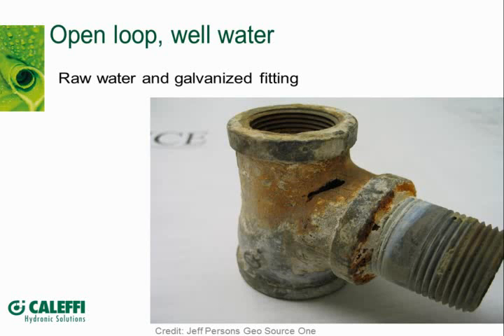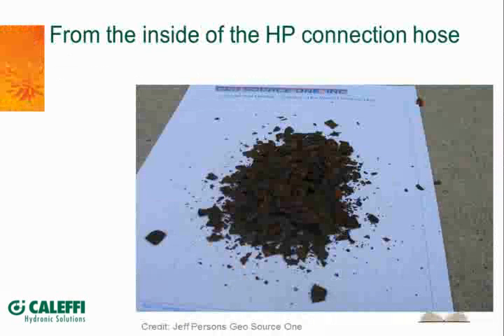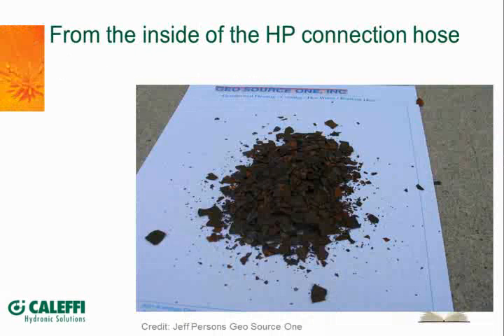I'd say within about 18 months of the depletion of an anode rod in a hot water tank, if you have an aggressive soft water, is about the time you see that tank perforated someplace where the water can get through to a raw steel area where a threaded coupling comes into the tank, or where there might be an imperfection in the glass lining on the tank. Well, now on this one here, the water too had something to do with it, because that's the electrolyte, I guess, in it. So the condition of the water can make that speed up or slow down. Like I said, the water and the hot water too would make that happen quicker.